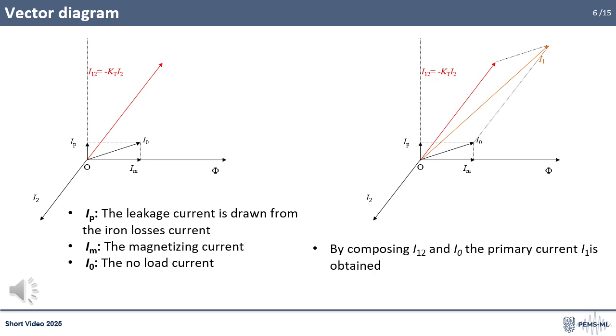On the right, we move to the real case. Here, part of the primary current is used to magnetize the core, that's the excitation current, I0. Because of this, the total primary current I1 isn't perfectly opposite to the secondary current anymore. What about that little angle between I1 and I12? That's what gives us the ratio and phase errors, the practical limitations that every real CT has.